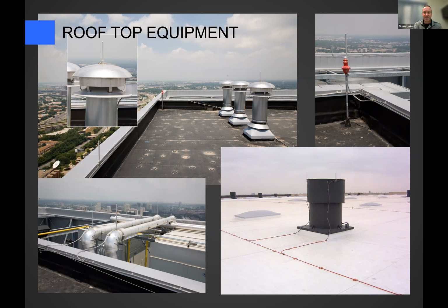If they're 6 meters long, you're going to have a lightning rod at each end and probably at each corner, right, to get within that 600 millimeters. Down in the bottom left, those are big cooling pipes. I bet those cooling pipes are thick enough to take a direct strike by themselves, but you know what isn't is the insulation, the thin metal over the insulation, the heat trace wiring in there. So even though the pipes themselves probably wouldn't take much damage in a strike, the associated equipment and the insulation and stuff, it would. So again, we put lightning rods on top of that.